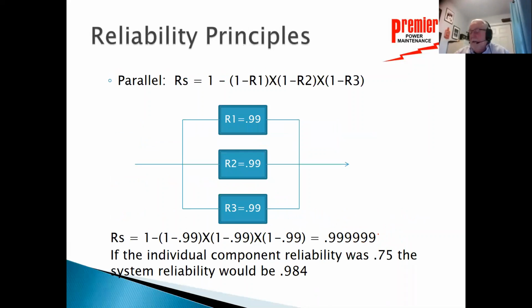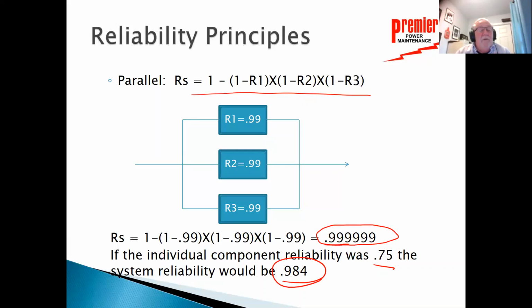Now, when we look at the reliability with regards to parallel systems, we have a totally different equation here. And I'm not going to spend a lot of time on equations because that can just eat up time and it's boring. But in this situation, we start out with each individual component having a reliability of 99%. And we look at the overall system reliability, it's almost 100%. And even if we took each individual component of this system and the individual components were reduced all the way down to 75%, the overall system would still be 98.5% reliable.